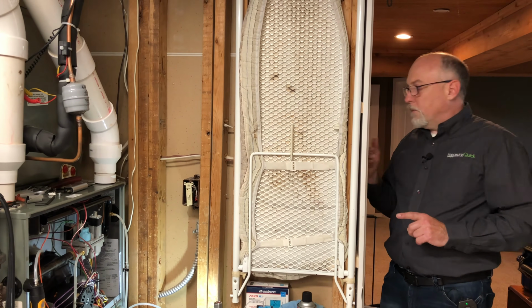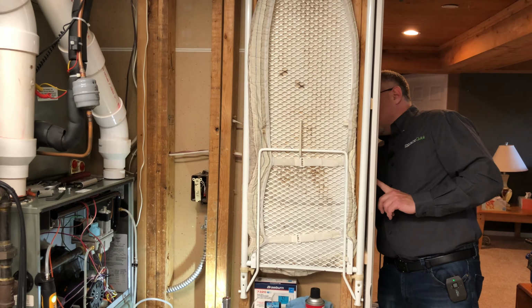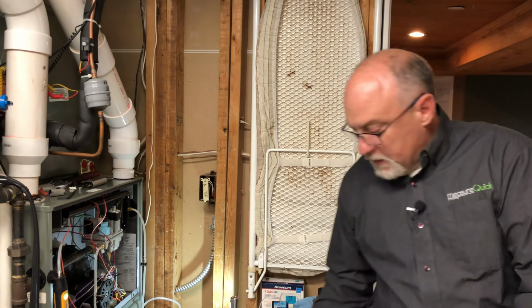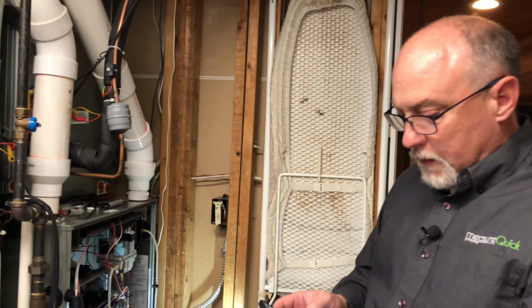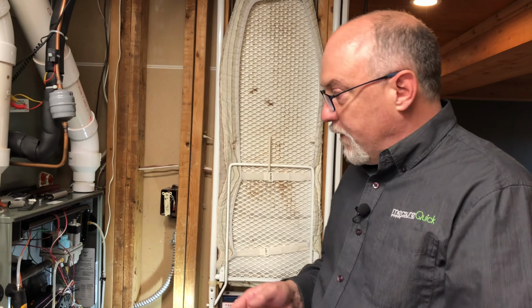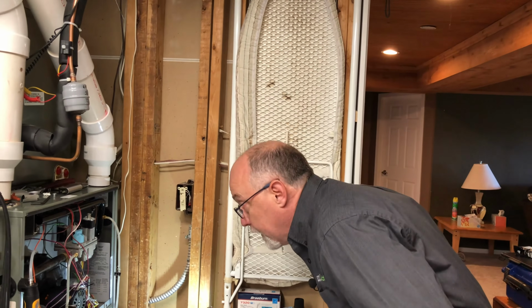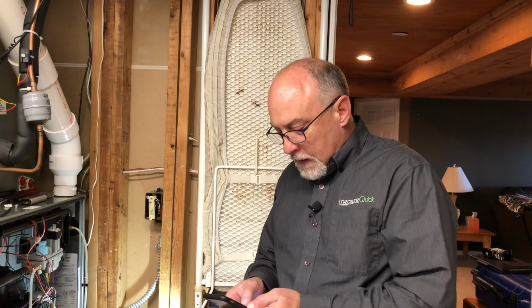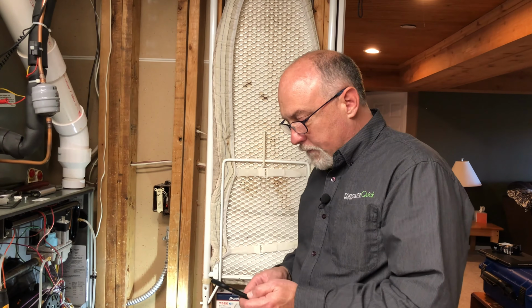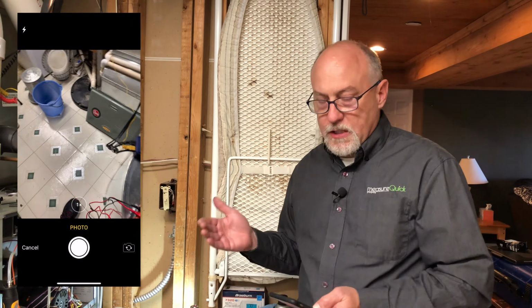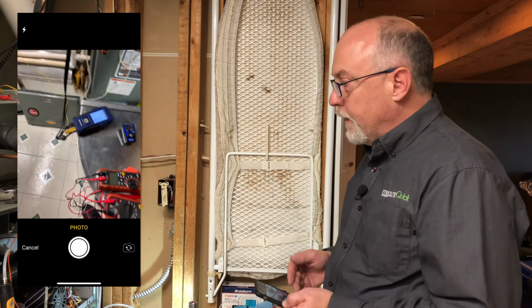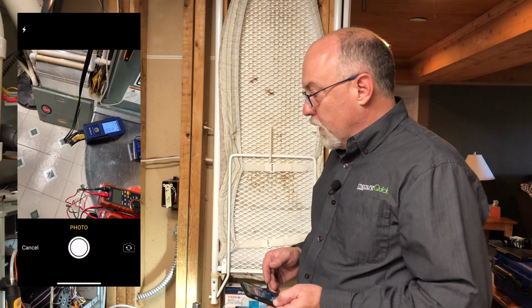And this all comes from the, we'll turn it up to 75. This all comes from the AHRI manual here. So when this furnace lights off, I'm going to watch my burner, and obviously my blower's not started yet, so when I hear my blower come on, I want to make sure that flame is stable. And I might get a picture here of just the condition of the flame, just to document that as I go. So we'll let that light, and we'll go ahead and get that photo.